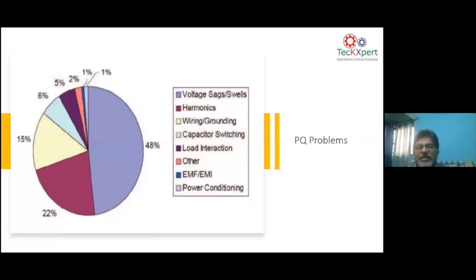How does it get amplified? For example, when you have a balanced network, and let's say you have a proper neutral, in a balanced network the neutral has to be always at 0. But when you have a voltage sag or swell, the neutral point gets affected. Now, as you know, when there are harmonics, certain harmonics flow through the neutral. I will come into that subject later. But when you have a voltage sag or swell, if the neutral ground voltage goes up substantially due to improper wiring and grounding, the problem can be due to wiring and grounding, but you may sometimes blame it on harmonics, which is not true.